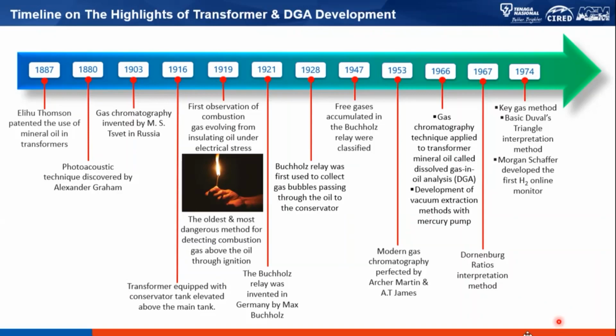So these gases are actually combustion gases. For example, hydrogen is very combustive, so this test is very, very dangerous. Then, since they realized that these gases were generating from within the transformer, the Buchholz relay was invented by none other than Mr. Buchholz himself. I forgot the first name of Mr. Buchholz. And then in 1947, we have free gas accumulated in the Buchholz for the first time, and it is being classified. So here we know that it comes from hydrogen, methane, acetylene, ethylene, etc.